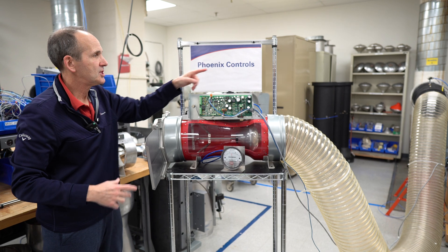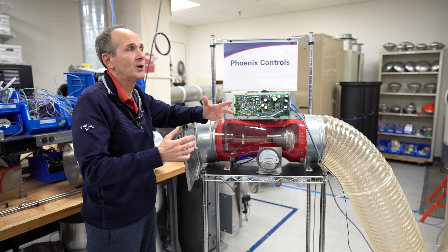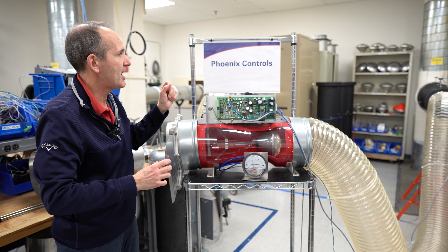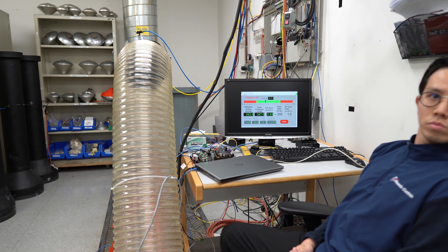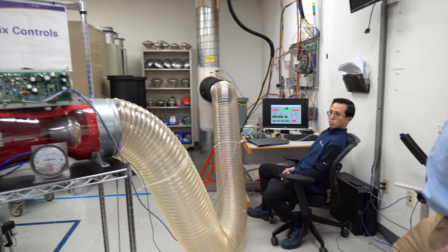Now if I bring this back, you see how fast that thing reacted. This is kind of anticlimactic compared to what you have to go through in the Phoenix 101, where they're going to give you a lot of detail about this. But at the end of the day, it works. I can go all the way and come back and you'll see it pop right back within a second. Pay attention to that — you notice it took a second. The reason is because the air station is using this up inside about 75 feet of air duct. This will slow down really fast if I shut it off, but then it's got to start up again.